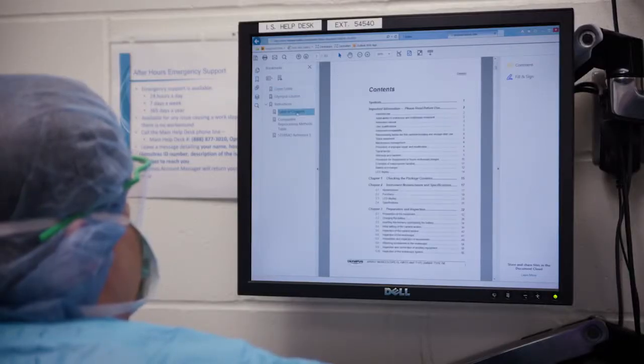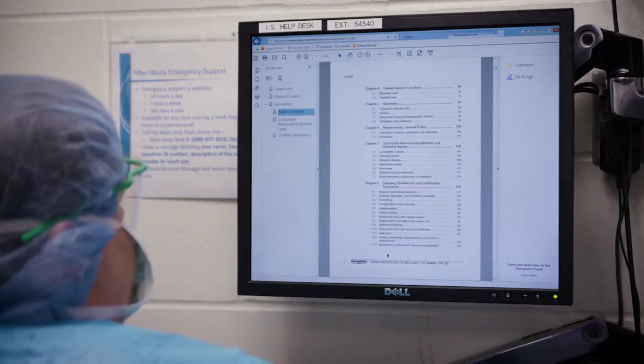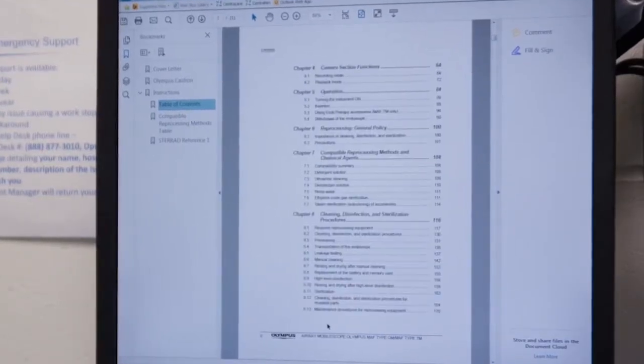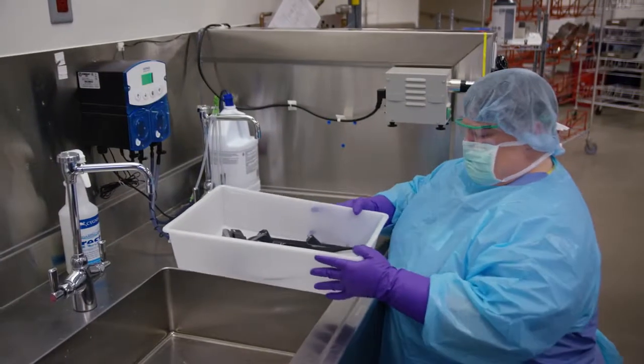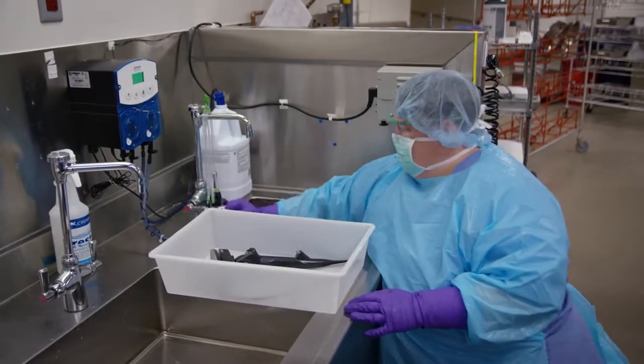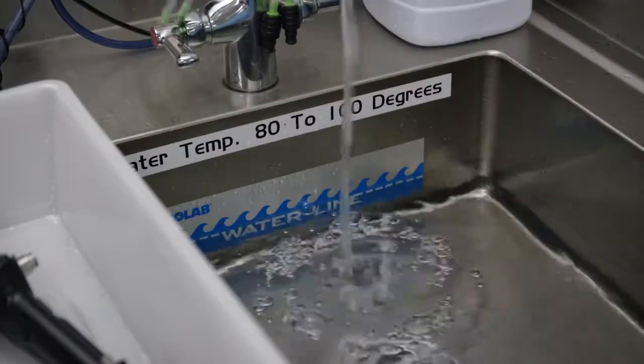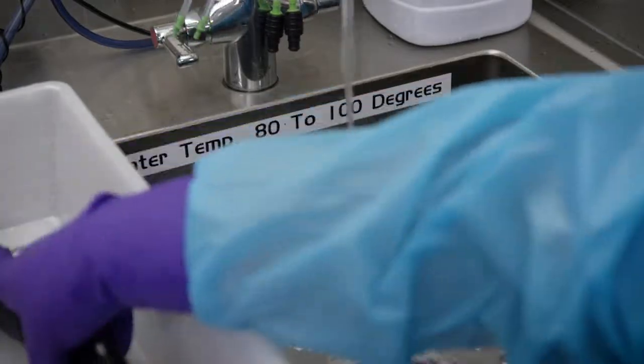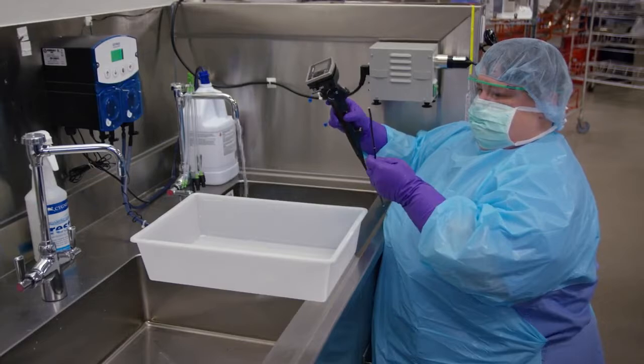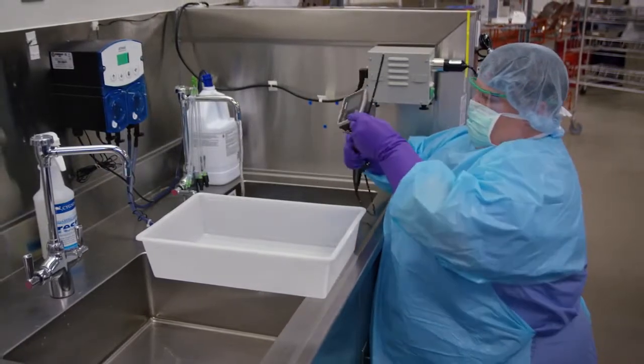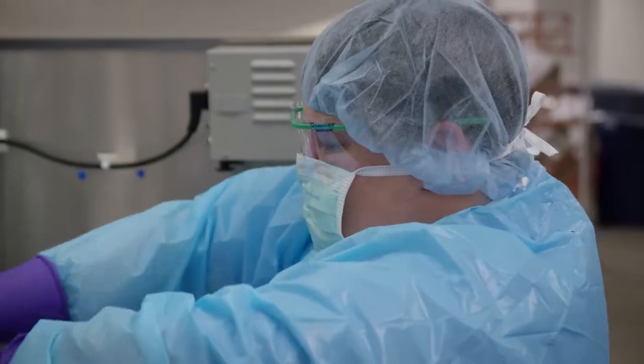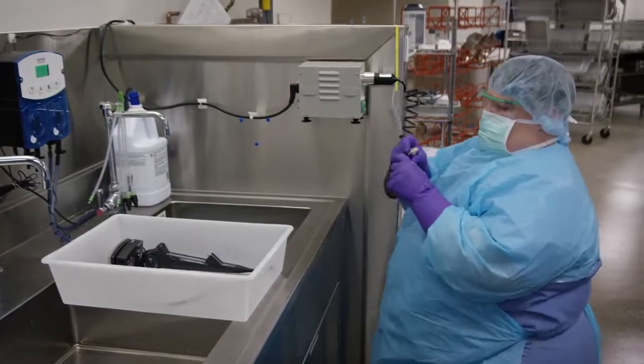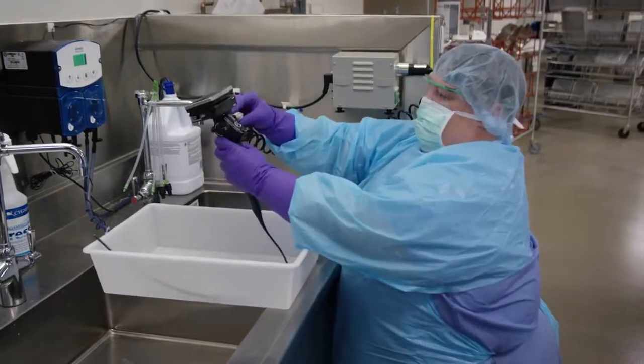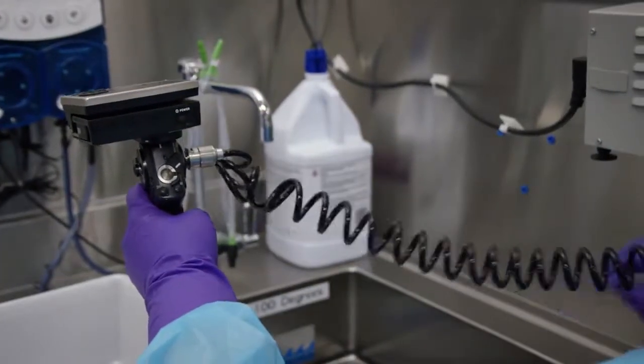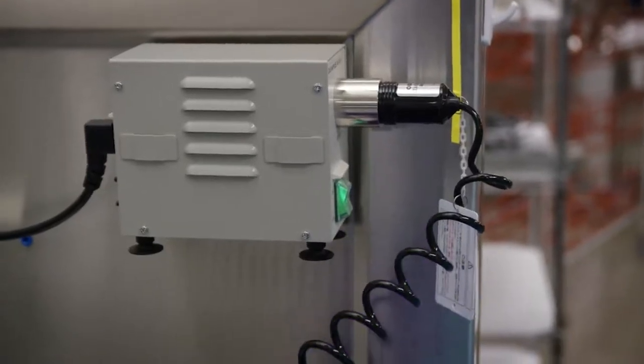Leak testing can be wet or dry, manual or mechanical. Select the method appropriate for the specific endoscope and follow the leak tester IFU. If conducting a wet leak test, fill the sink or basin with the proper level of clean water. You'll want an area large enough to accommodate a minimally coiled scope. Visually inspect the scope for tears, holes, or obvious signs of wear and damage. Attach the leak tester to the venting connection, ensuring the cap is fully on and locked.